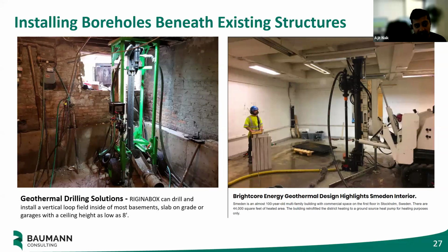DC now does permit underground boreholes under buildings and in existing structures. There are limits as to how close they can be to the property line, but this is possible. When people tell you it's not feasible because the building already exists, that's not true—these technologies are out there, and people are using them. Of course, just like digging outside, there's call-before-you-dig: you have to coordinate with whatever underground utilities, subways, or other things are down there. But as long as you're coordinated, you can go beneath the building—existing or new—just as well as you can out in the green field.